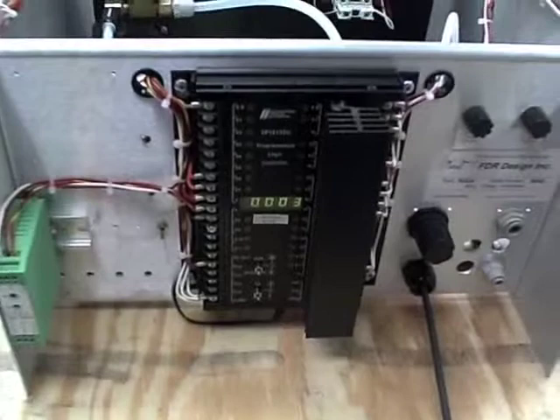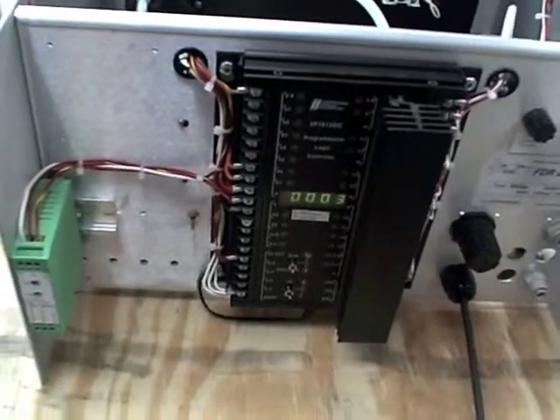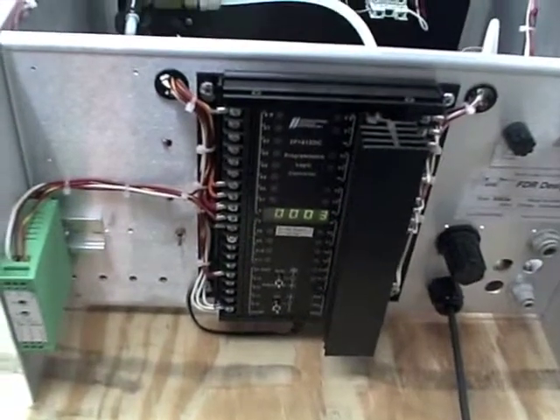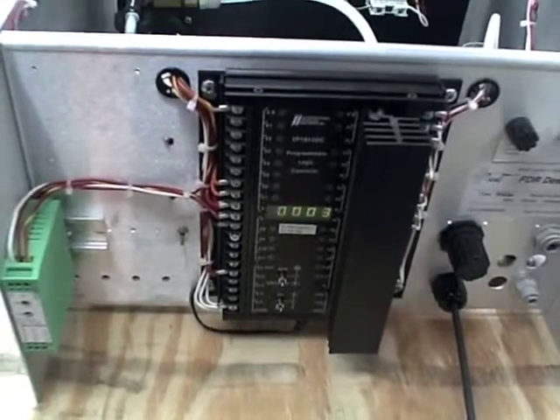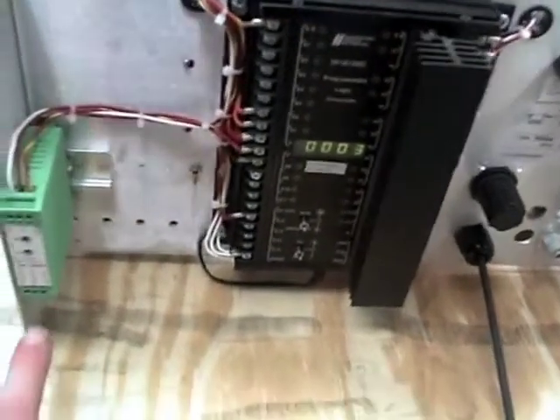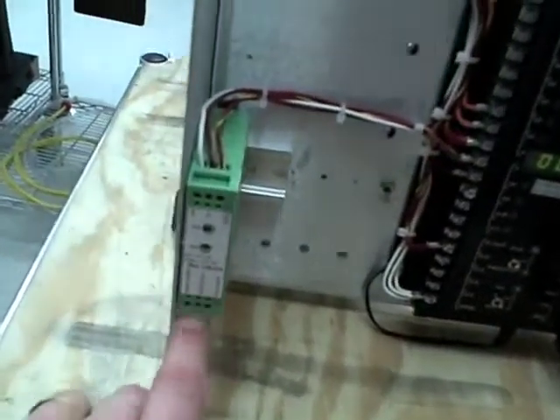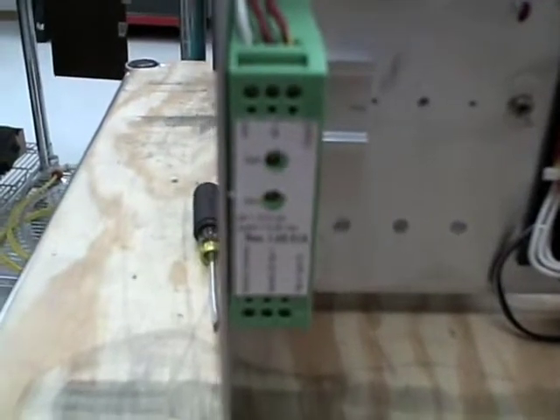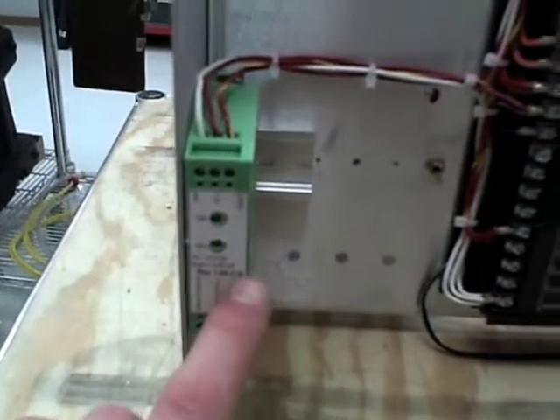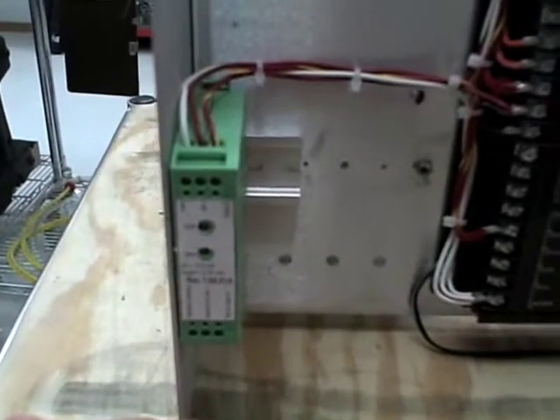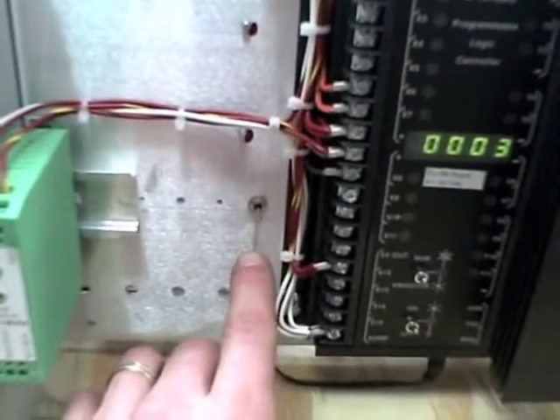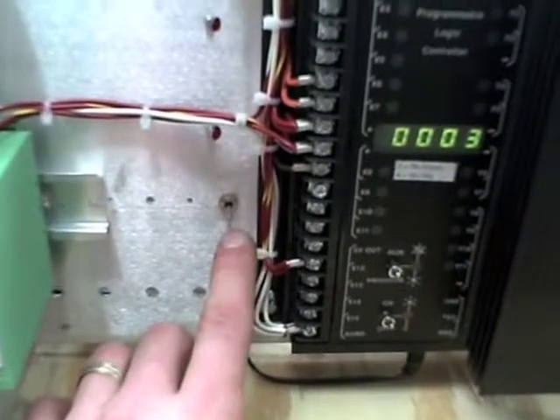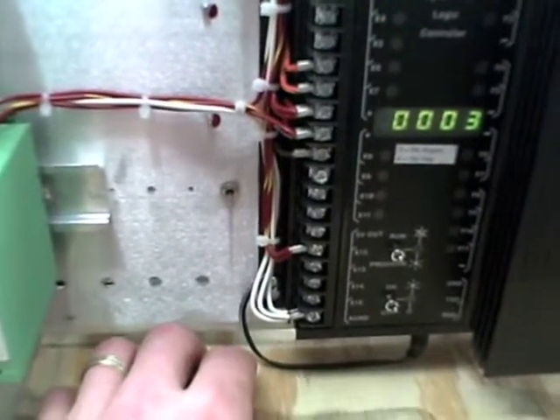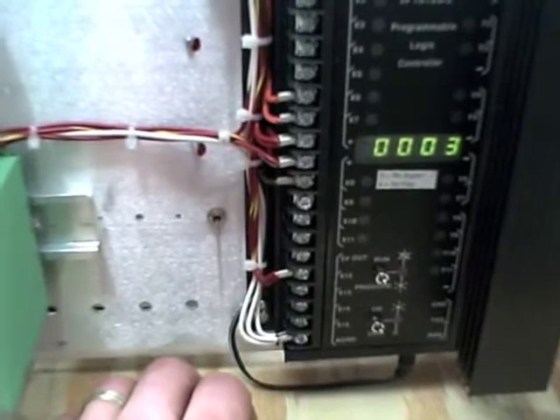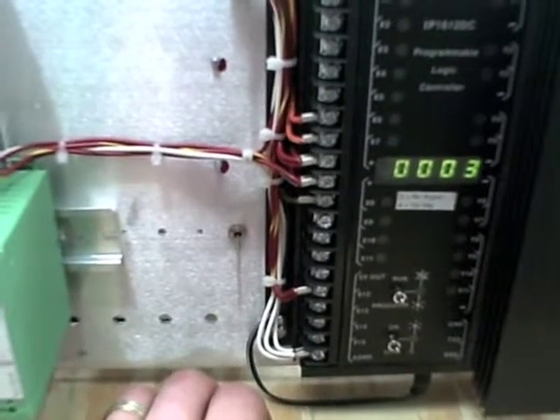Back of the machine, we'll notice a couple key components, and this is where a lot of the work gets done on a regular basis with calibration and changing fuses if they might blow, or adjusting the pressure. And we'll start on the left here. This is the argon amplifier board, and you can possibly see the revision 1.68.01A, and the A again is for argon. We can set these up for different types of gas. Over here is going to be the sensor override switch. So when you're doing the calibration, you want to throw this in the up position, and that'll keep the machine from beeping at the end of the cycle. It'll keep it running so that you can do the calibration.